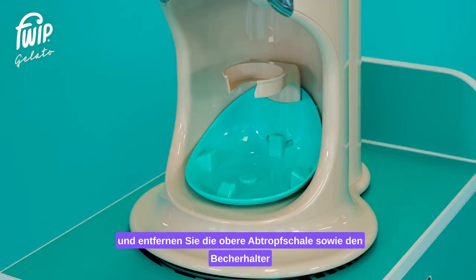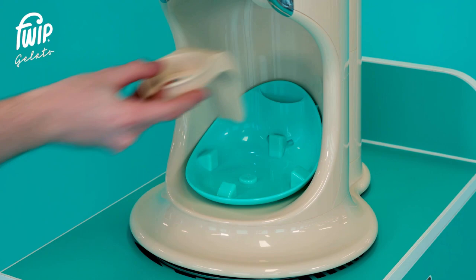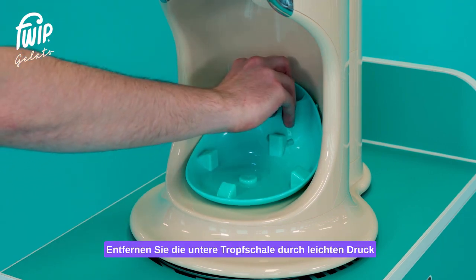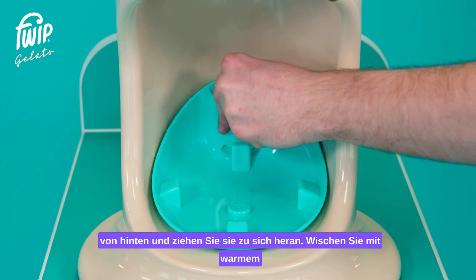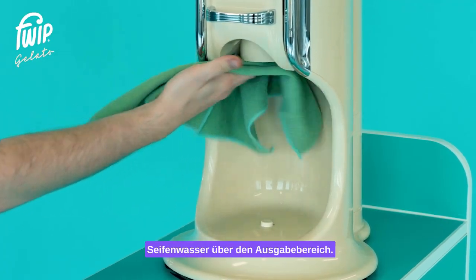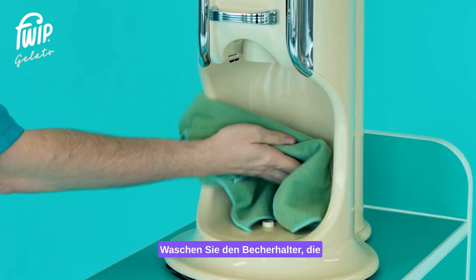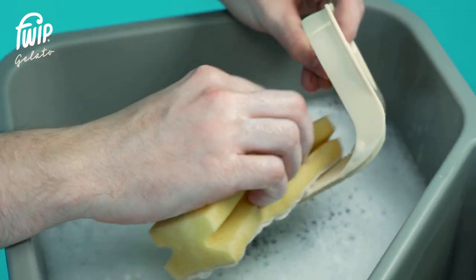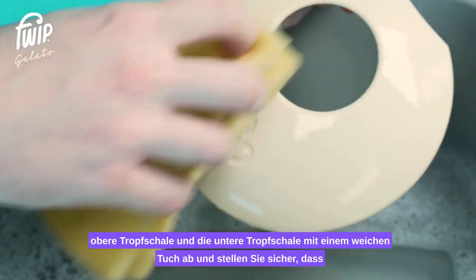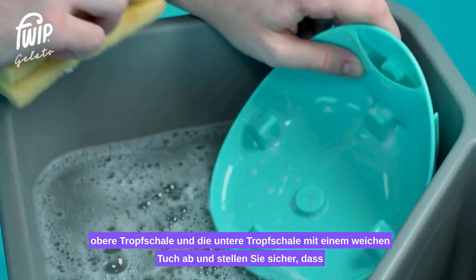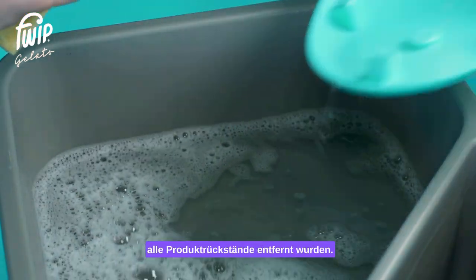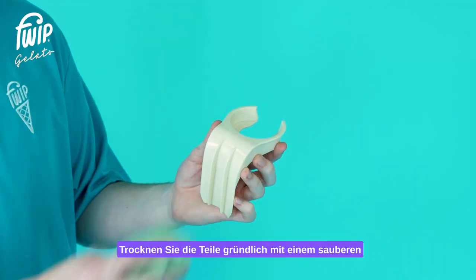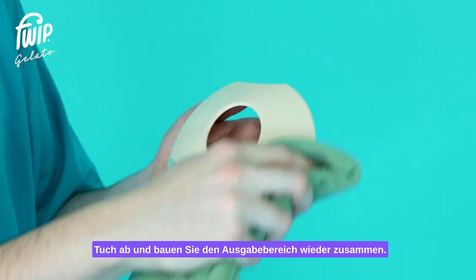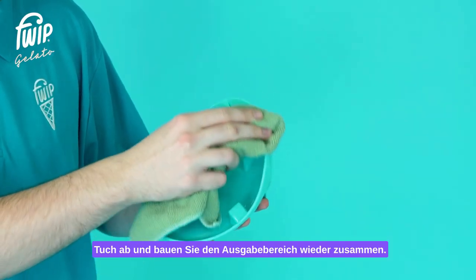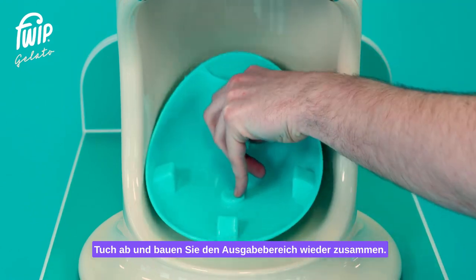Remove the upper drip tray and cup holder, and place to one side. Remove the lower drip tray, by applying gentle pressure from the rear, and pulling towards you. Using warm soapy water, wipe around the dispense area, using a soft cloth. Wash the cup holder, upper drip tray, and lower drip tray, ensuring all product residue has been removed. Thoroughly dry the parts using a clean cloth, and reassemble the dispense area.